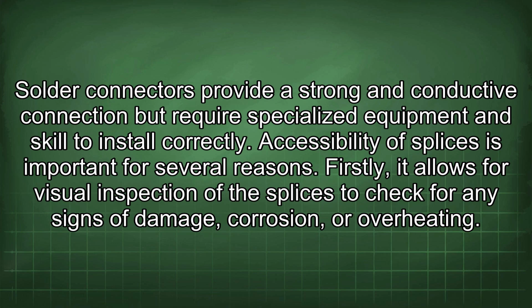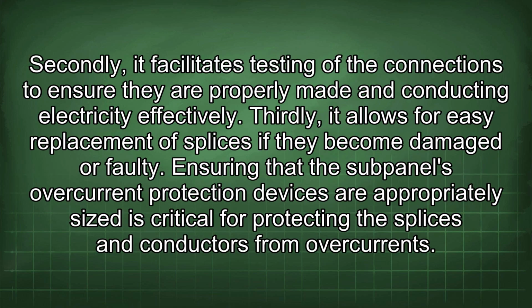Accessibility of splices is important for several reasons. Firstly, it allows for visual inspection of the splices to check for any signs of damage, corrosion, or overheating. Secondly, it facilitates testing of the connections to ensure they are properly made and conducting electricity effectively. Thirdly, it allows for easy replacement of splices if they become damaged or faulty.